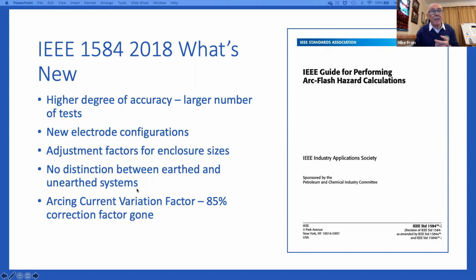And adjustment factors for enclosure sizes have come in now, and they've dropped the distinction between earthed and unearthed systems with the new reprint. And finally, the arcing current variation factor has come in, whereas before there was an 85% correction factor. What we mean by that is, at low voltage in particular, it's important to carry out an incident energy level calculation, but then apply an 85% correction factor to lower the arcing current, which will lower the arcing current, obviously, but it may increase the amount of time it takes to trip. And paradoxically, that could actually create the conditions where the incident energy level for the lower level of arcing current could be higher.